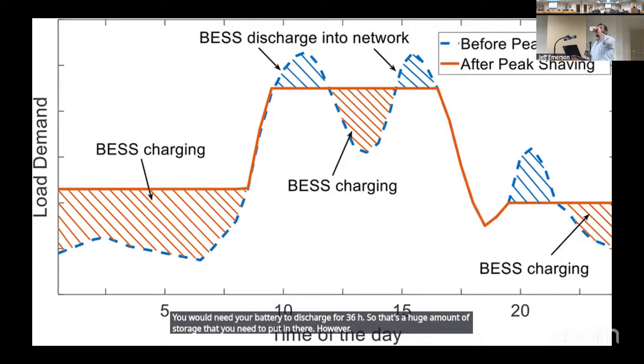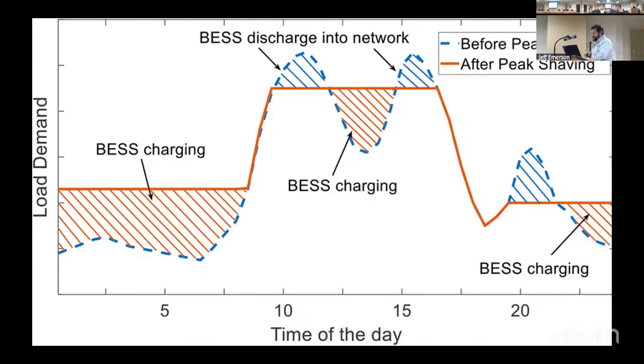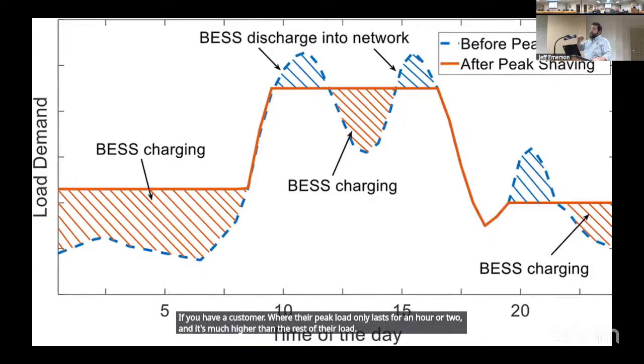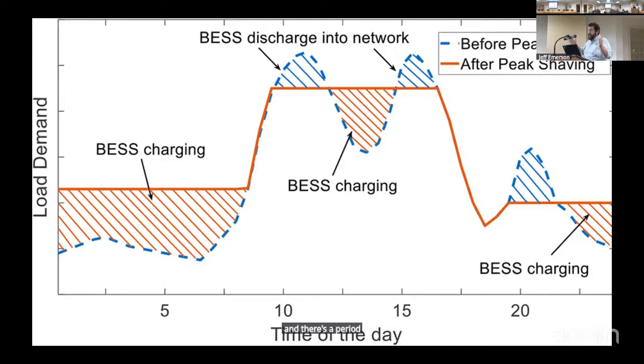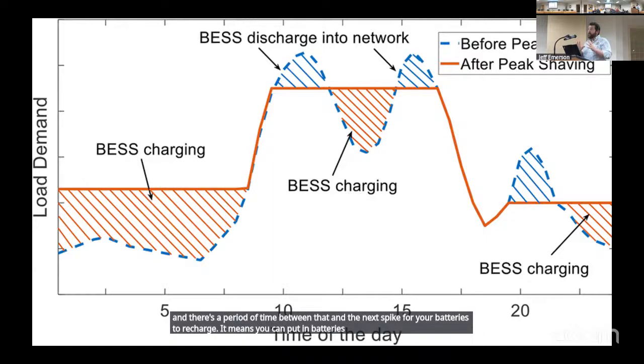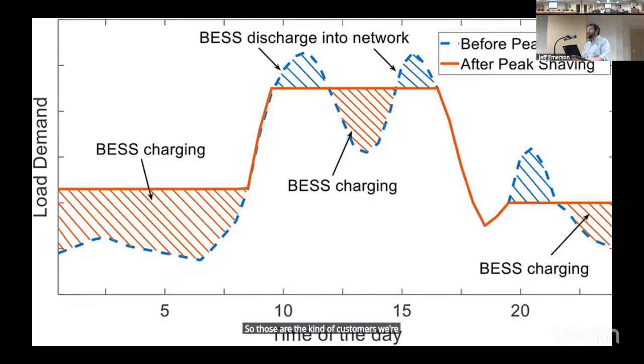However, if you have a customer where their peak load only lasts for an hour or two, and it's much higher than the rest of their load, and there's a period of time between that and the next spike for your batteries to recharge, it means you can put in batteries that have a low energy storage but a high power output, and they're relatively inexpensive compared to the amount of value they can bring to that customer. So those are the kind of customers we're always looking for, batteries generating value to that customer, but also generating a ton of value back out to the grid too.